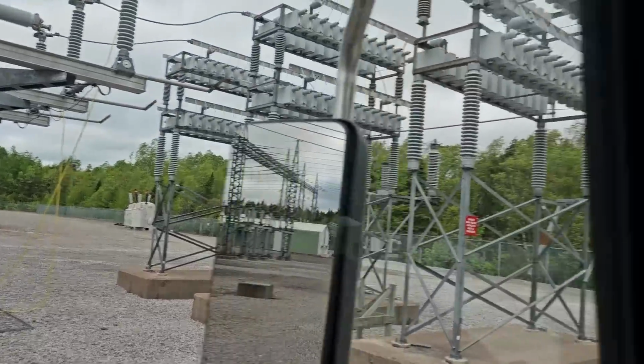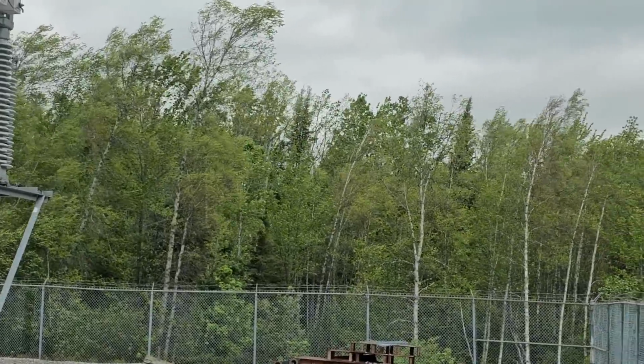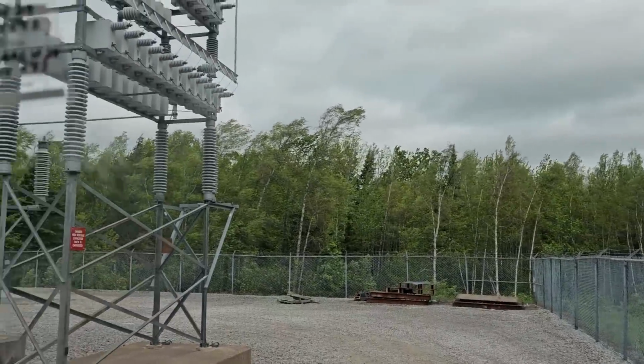What causes the current to lag the voltage is inductive loads. There's a lot of inductive loads out there. A transformer just being tapped onto the line, the coils cause lagging power factor. Heavy industrial customers, you'll often see capacitor banks to correct the power factor because of all the machinery that causes that lag. The reason I wanted to take a look at this, let's flip the camera around, it's more interesting than my face. And I'll be sitting in the truck because it's pretty windy out there.